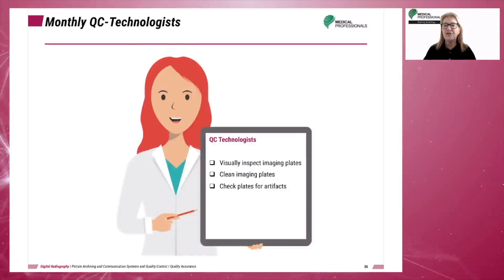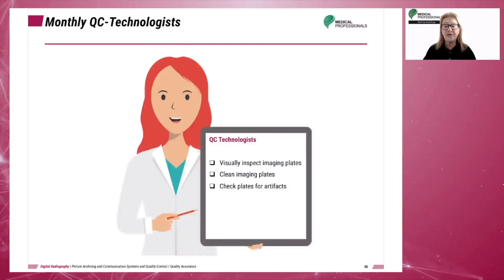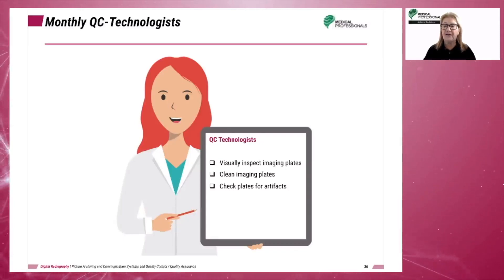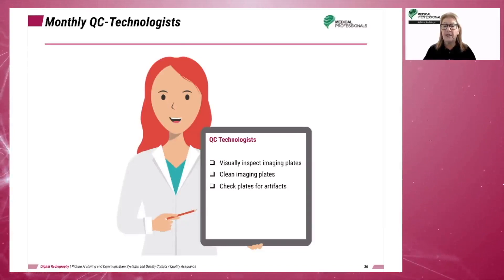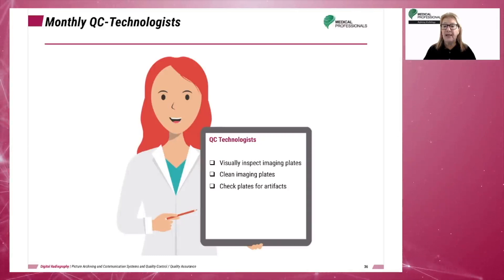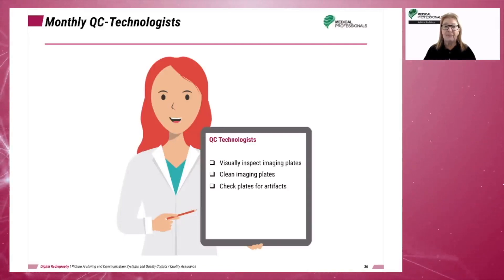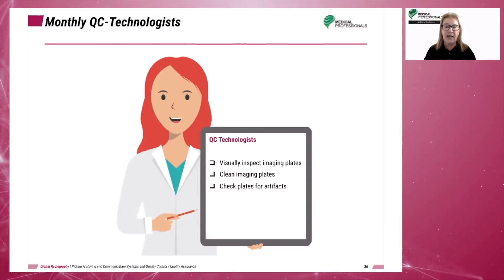In addition to the reject analysis, technologists may be responsible for inspecting image receptors for dirt, damage, and artifacts. Plates may be cleaned using cotton gloves and manufacturer-recommended cleaning cloths and solutions. If artifacts are a result of damage to the image receptor and cannot be remedied, the image receptor needs to be disposed of according to State and U.S. Environmental Protection Guidelines.